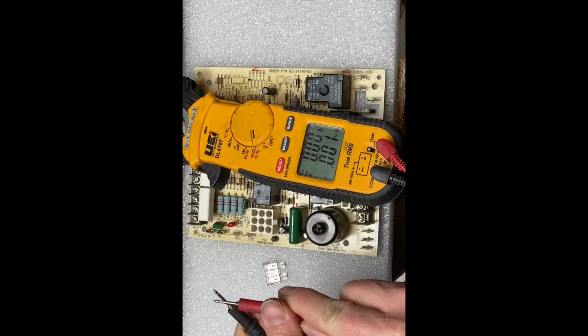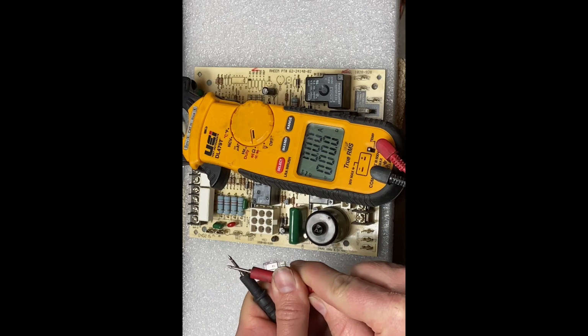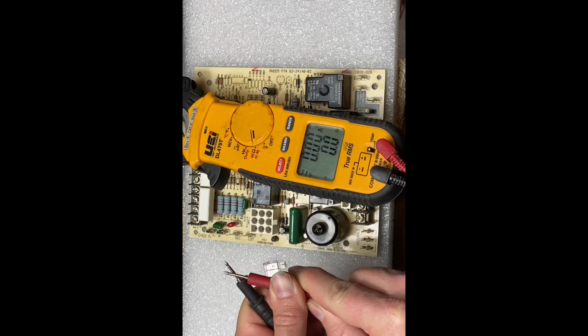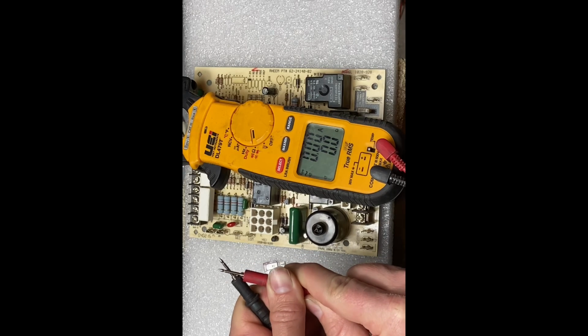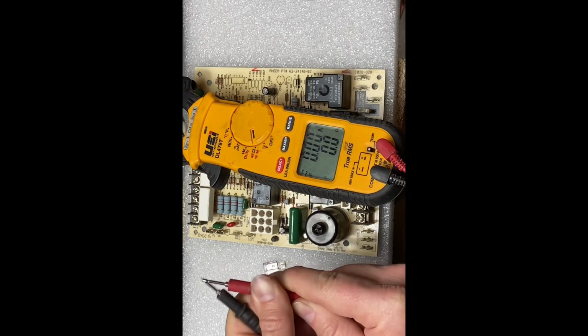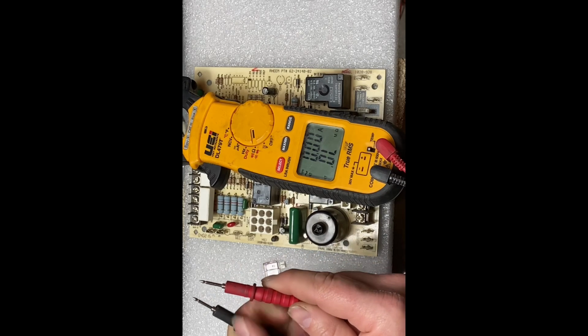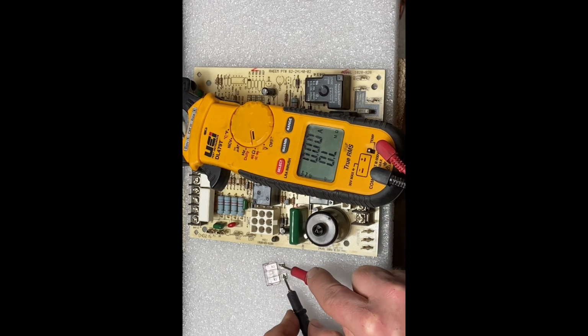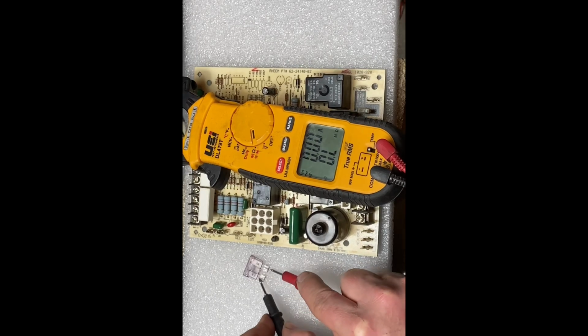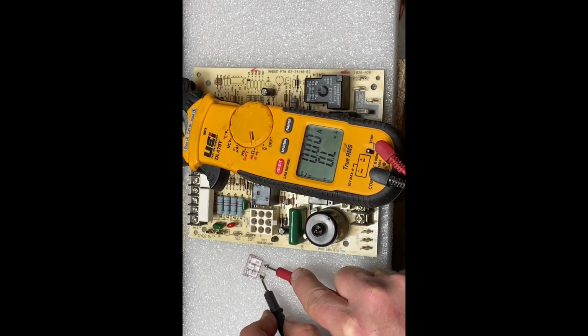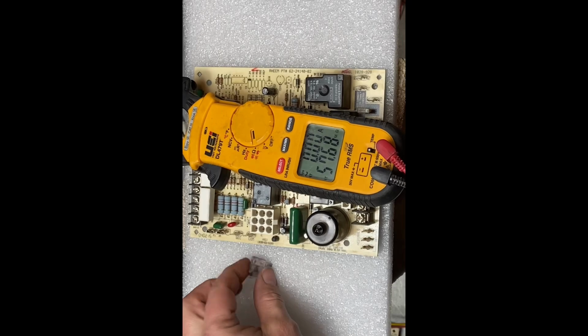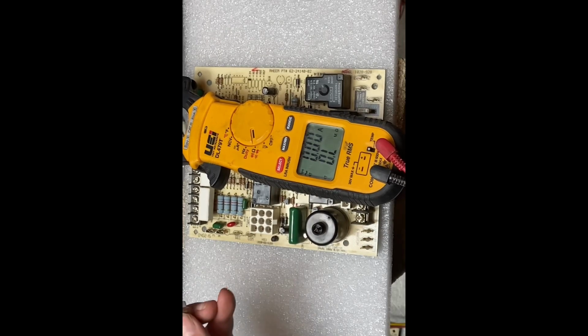So if I'm reading this number here being, oh, now we're reading 0 ohms. That's what it should show. So that means the switch is closed. It's a good fuse, or it will show OL and open. So if I check the fuse itself, it's saying OL. So we know that this fuse is open, or this is a bad fuse.